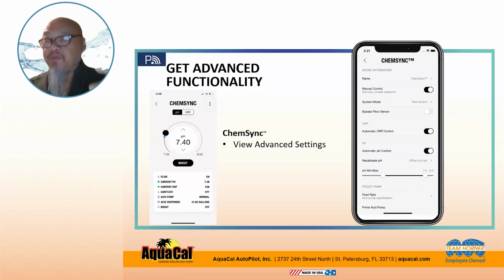So it's trying to control the pH, but there's no solution to bring the pH back down. So that's what the pH min and max ranges are for. Feed rate is basically selecting the acid pump. When you first install the ChemSync system, you've got this prime acid pump to, pretty much, put solution into the acid feed lines to go to the manifold assembly.